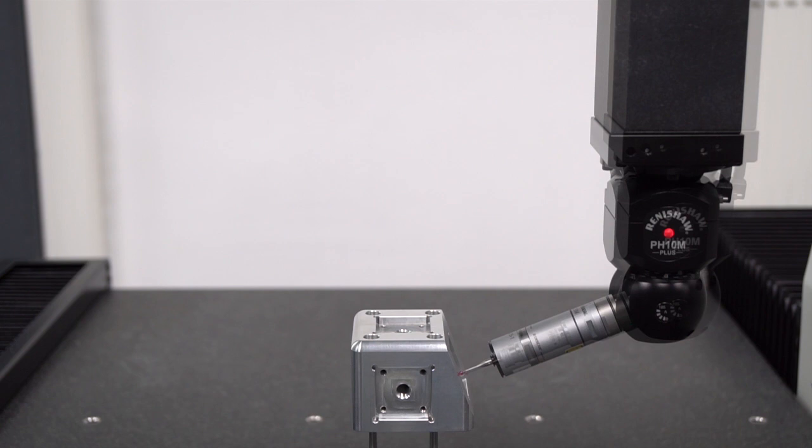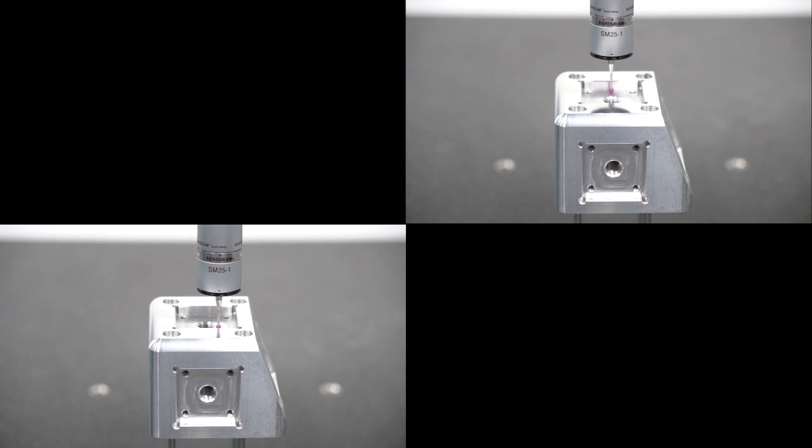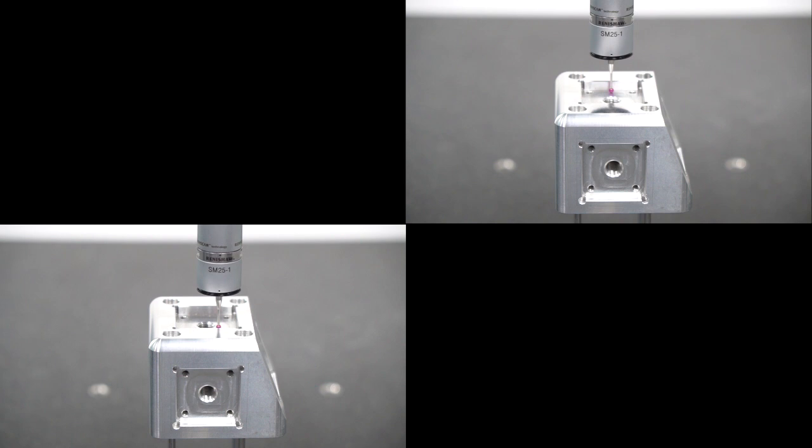For use in serial measurements, the machine can run in super fast mode. After measuring one part in standard speed, the following parts can be measured in super fast mode with nearly the same repeatability and be compared with the results of the first measurement.